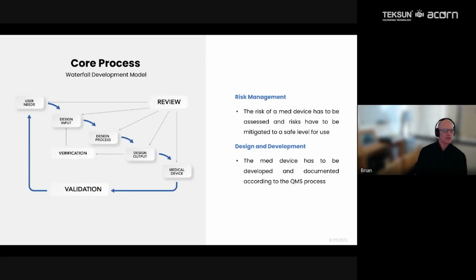And then the next part of this is the design process. That's typically where you're working through designing a new instrument, or maybe it's a consumable, and you're trying to design the product so that it meets all of the requirements that you had in the design input. And then once you've done the design, you can get parts made through design output. Design output could mean schematics. It could mean drawings. It could mean CAD models. All of these are design outputs. And then you would go through and build something, and then you would evaluate it. It's called verification against the design input. So you're basically confirming, did what I end up producing do all of the things that I determined it needs to in that design input?